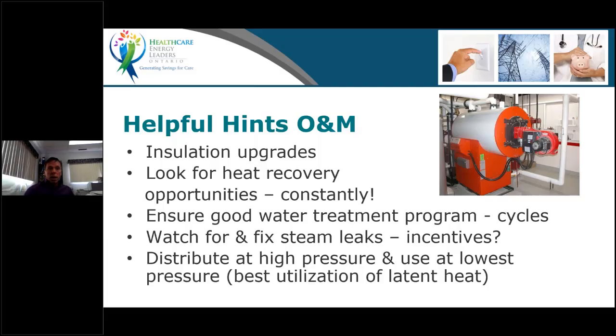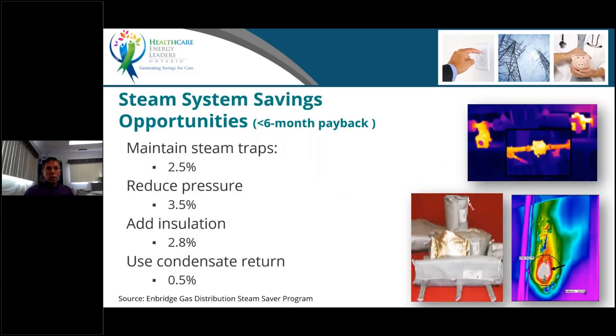Like I said before, if you do not, you'll end up with a lot of issues, which will reduce the efficiency of your system because there's going to be calcium buildup. There will be damage to your equipment. Other opportunities that are shown here with the quick payback: maintain steam traps, obviously, and if you can reduce the pressure compared to what you're using right now, adding insulation.